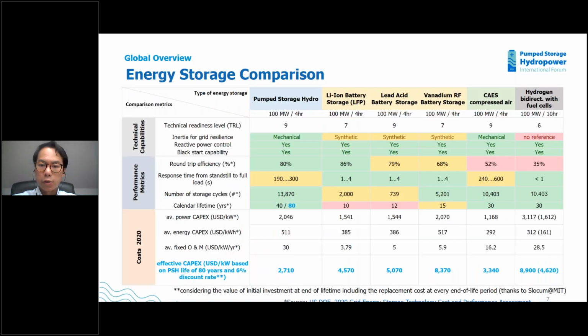This can be further illustrated with a simple cost comparison. Based on the latest US DOE Energy Storage Cost Assessment Report, we compare a table on 100 megawatt, 4-hour energy storage systems. As you can see, pump storage and chemical batteries are all capable of providing inertia, reactive power control, and black start. However, when we look into the capex for power and energy, pump storage has a higher capex than lithium-ion battery on paper for a 4-hour discharge duration system.